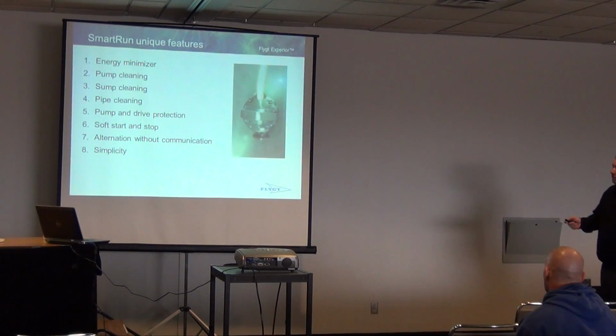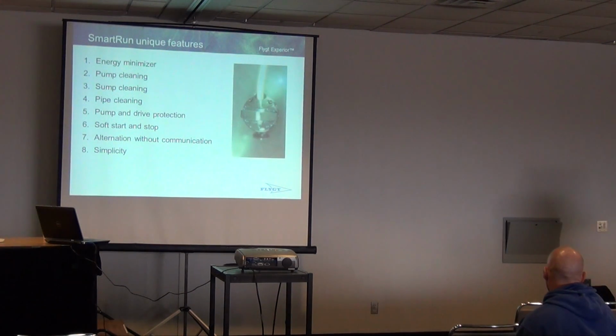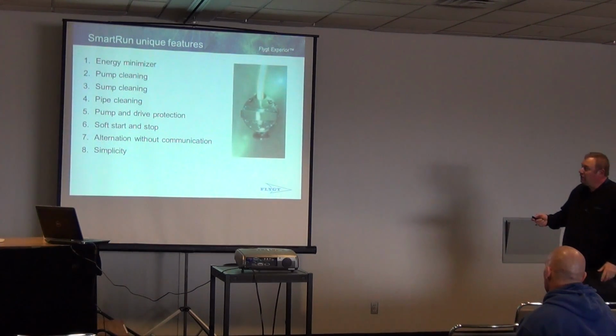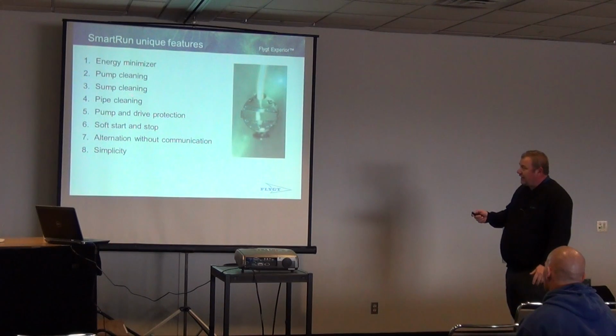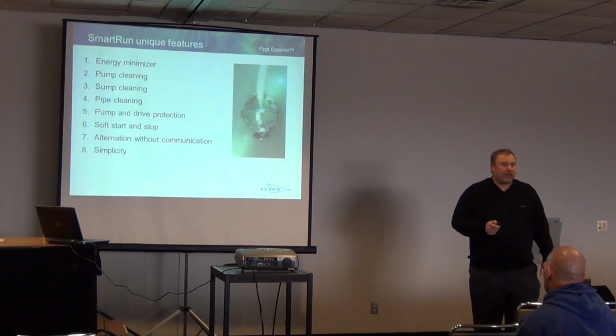So what that really means is anytime we slow a pump down, the concern becomes, what's my scouring velocity? Am I keeping my 2.5 feet per second to keep my materials moving through my force main? That's always a concern anytime you slow a pump down, and that's a concern that we always get asked. Well, again, a programmable function is pipe cleaning.